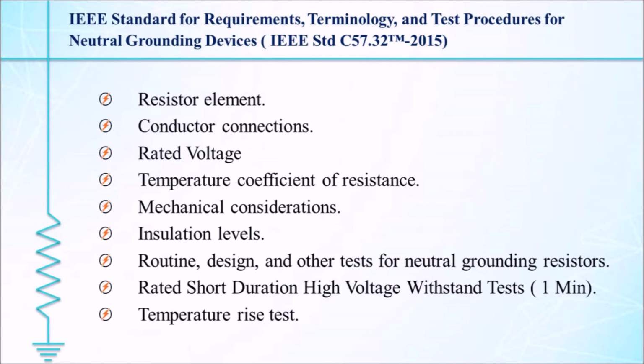And an other test is a test performed on one or all units of a specific design if required by the purchaser and is usually requested to demonstrate conformance to special application requirements as opposed to the more general application requirements covered by a design test. A rated short duration high voltage withstand test for 1 minute.